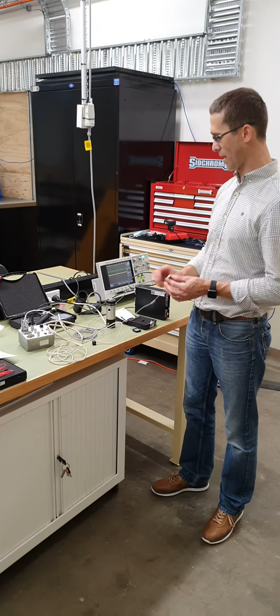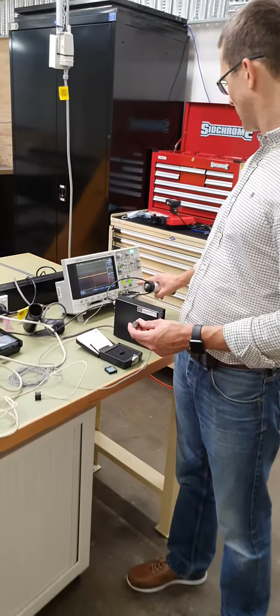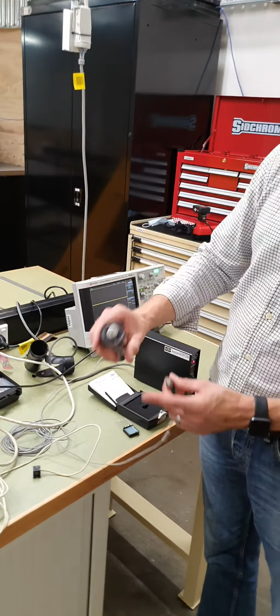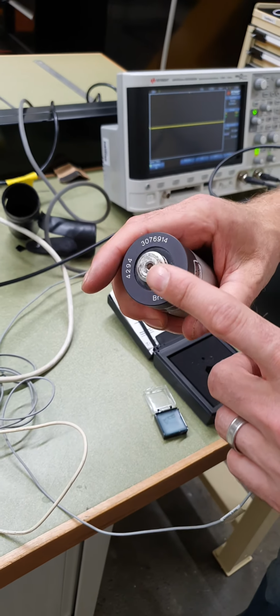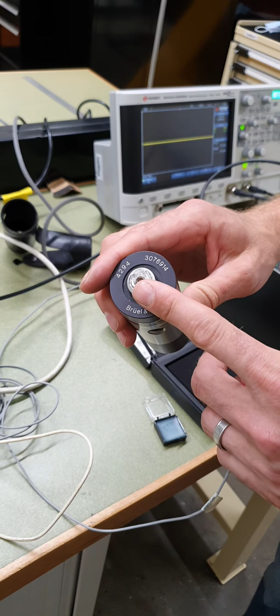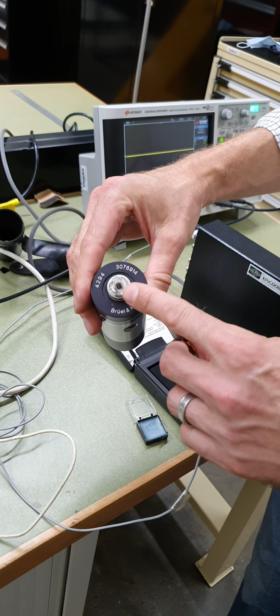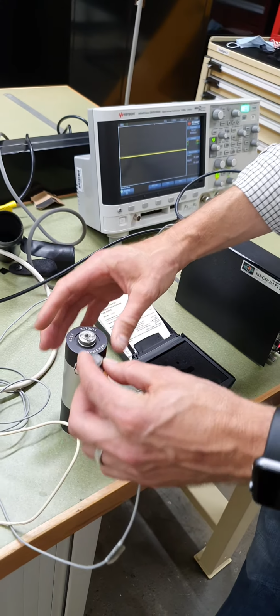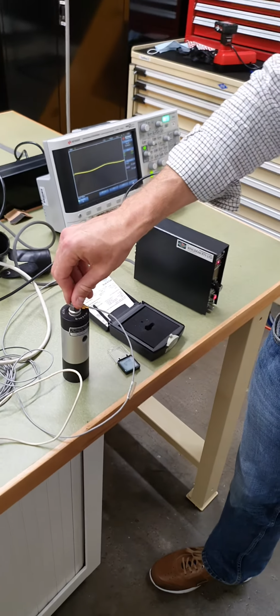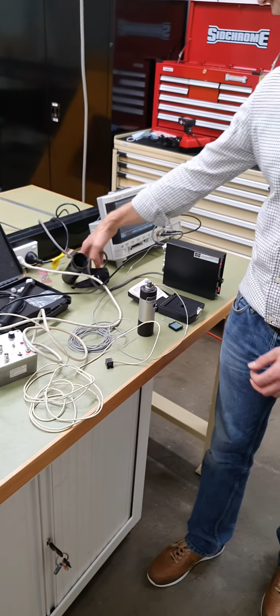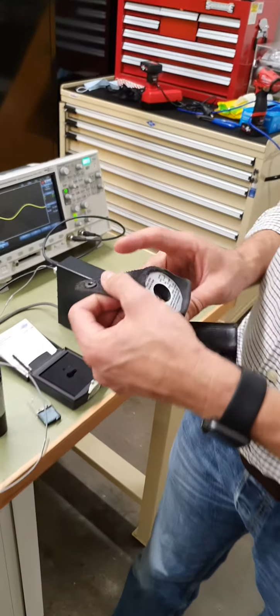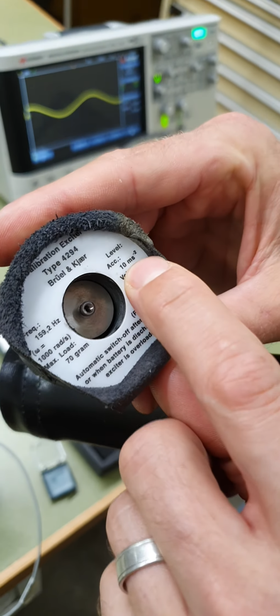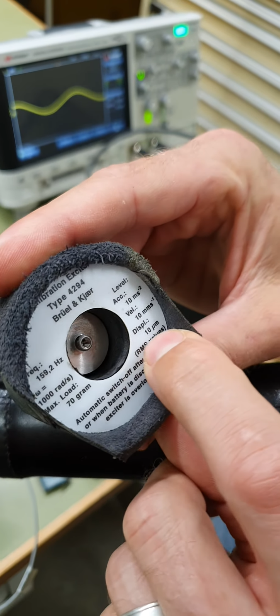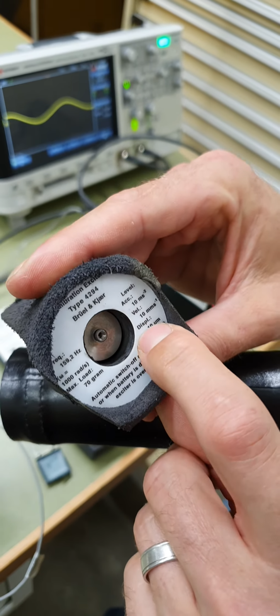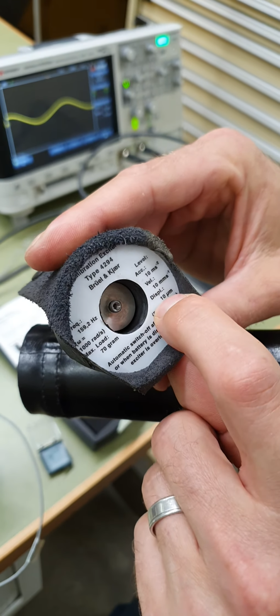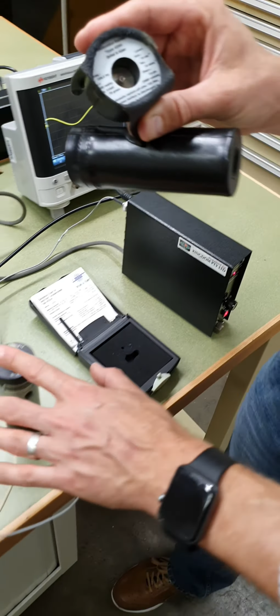What else? I can show you also how to check and calibrate your transducer. So let's demonstrate this accelerometer calibrator here. This is essentially a shaker. It vibrates at 159.2 Hertz at 10 meters per second squared RMS. The reason for it being at 159.2 Hertz is that that corresponds to an angular frequency of 1000 radians per second. Because of that, 10 meters per second squared is the same as 10 millimeters per second, which is the same as 10 microns of displacement, acceleration, velocity and displacement respectively. And they're just useful values for this device to provide vibration at.